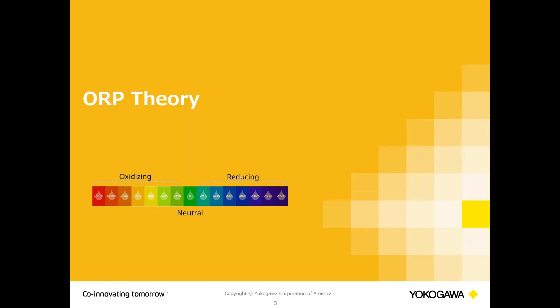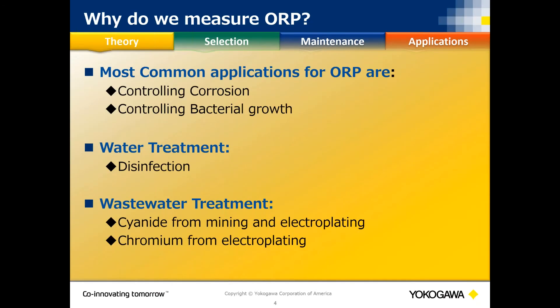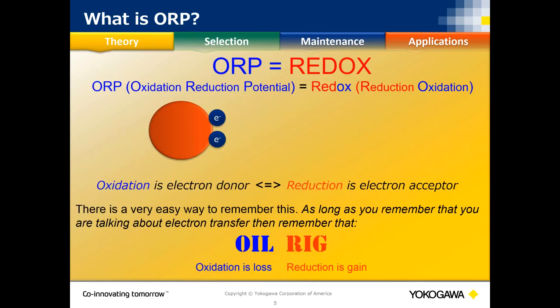Common ORP measurements in a plant include cooling towers for biocide growth and corrosion control. ORP measurements also indicate piping deterioration. For wastewater, plants dealing with cyanide or chromium from electroplating must go through two stages of ORP reactions to ensure that the chromium and cyanide exiting the plant are not in the toxic state that could harm the environment or living organisms.